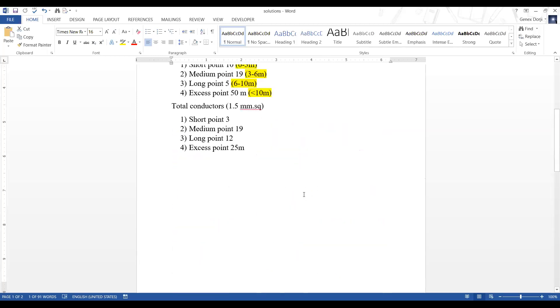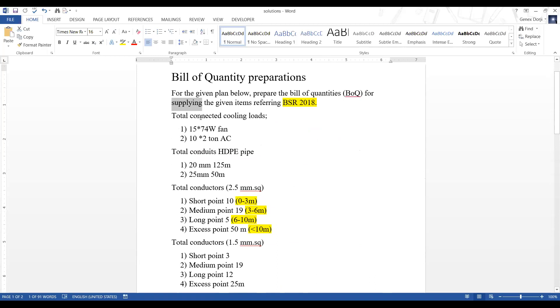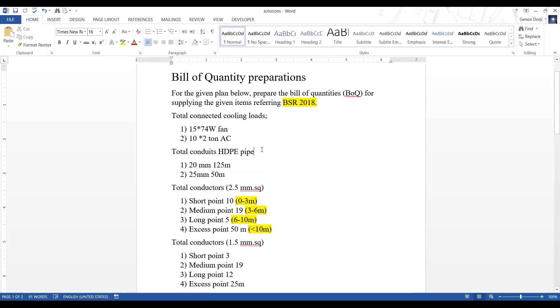For this plan, the total connected cooling loads required are 15 numbers of 74-watt fans and 10 numbers of 2-ton air conditioners. Now this is just for understanding - if you calculate the cooling load for that building it may not come to exactly 10 ACs and 15 fans. I'm just giving you an example of how to prepare the bill of quantities.